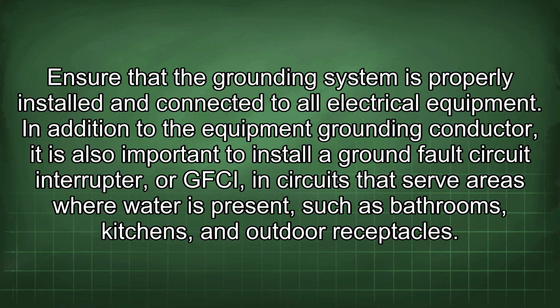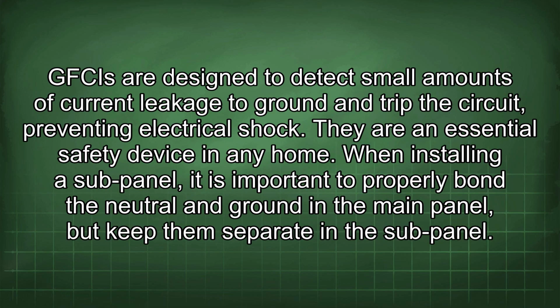In addition to the equipment grounding conductor, it is also important to install a ground fault circuit interrupter, or GFCI, in circuits that serve areas where water is present, such as bathrooms, kitchens, and outdoor receptacles. GFCIs are designed to detect small amounts of current leakage to ground and trip the circuit, preventing electrical shock. They are an essential safety device in any home.